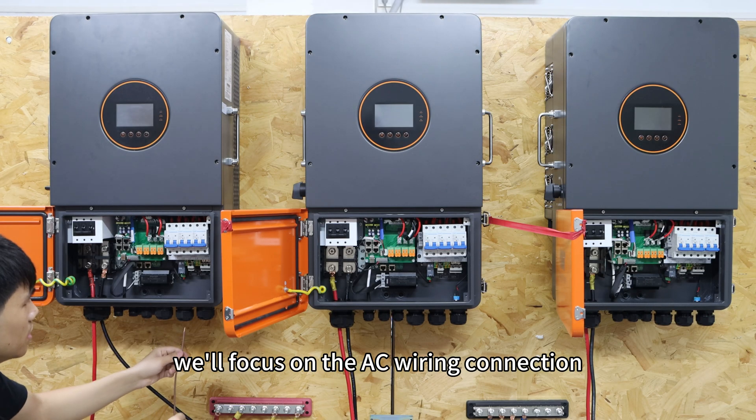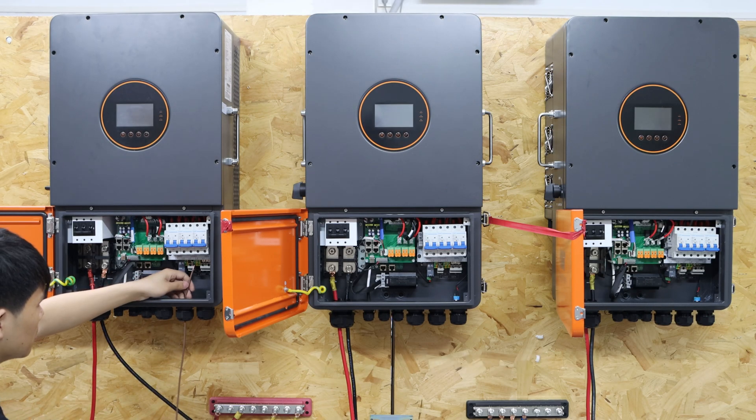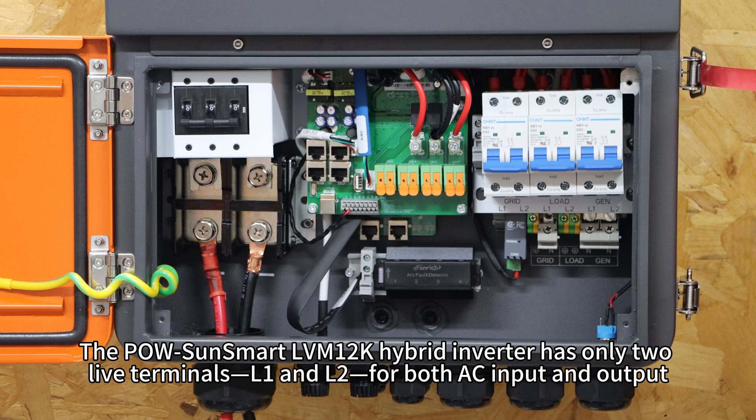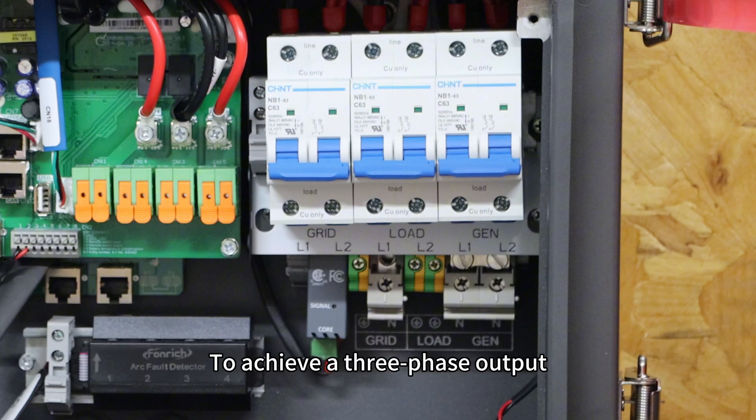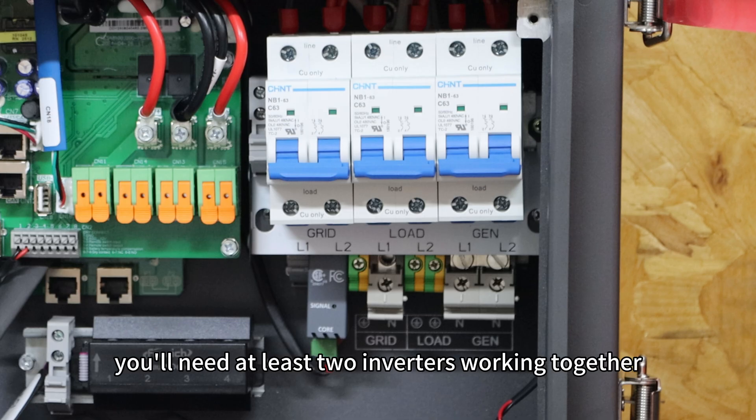Here we will focus on the AC wiring connection. The POW-SunSmart LVM12K hybrid inverter has only two live terminals, L1 and L2, for both AC input and output. To achieve a three-phase output, you will need at least two inverters working together.